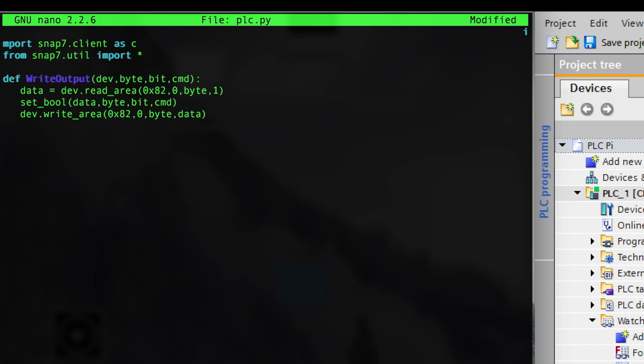Since SNAP7 doesn't really write bits, we need to read a byte area from hex 82. You can see dev dot read area at the hexadecimal 82 area. We read that, save it to data, then use a set bool function on that data we read, and manipulate that bit using the command. Then we write it back to the PLC. So we read some data, changed a bit in it, and wrote it back — that's basically what this write output does.